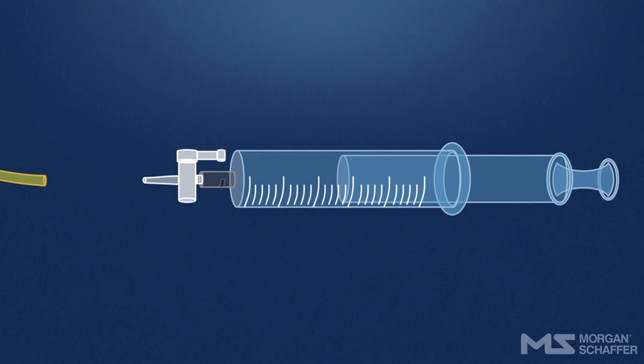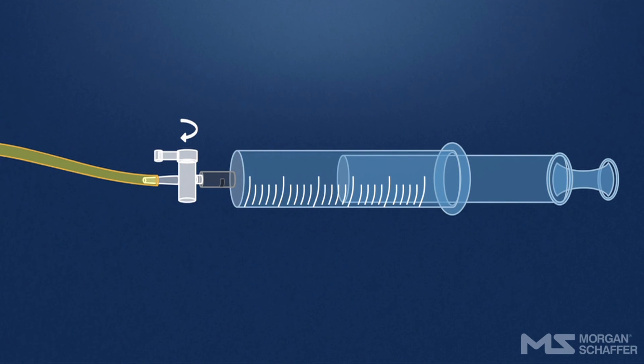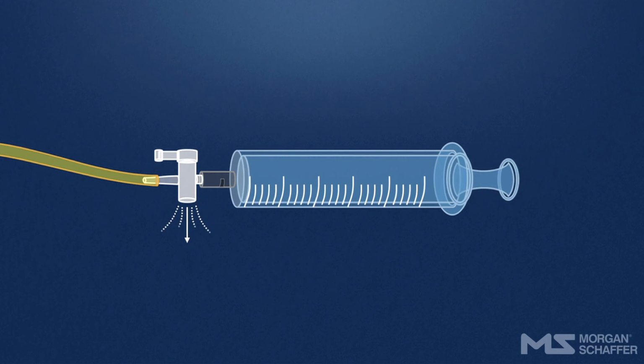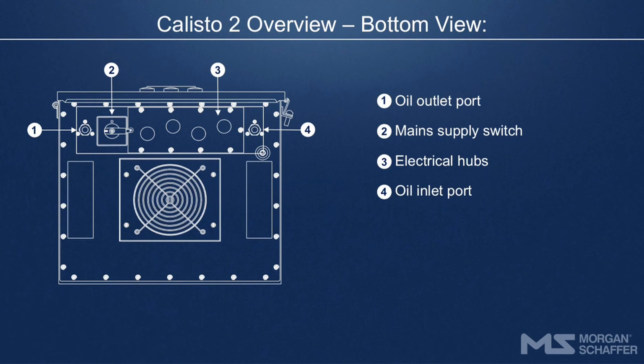Connect the Quick Connect oil sampling tube to a glass syringe fitted with a 3-way stopcock valve, typically a 30 cc capacity syringe or a shake test syringe. Turn the 3-way stopcock handle toward the top port and push the piston of the syringe all the way in to remove all air from the syringe. Connect the Quick Connect oil sampling tube into the monitor's oil sampling port.